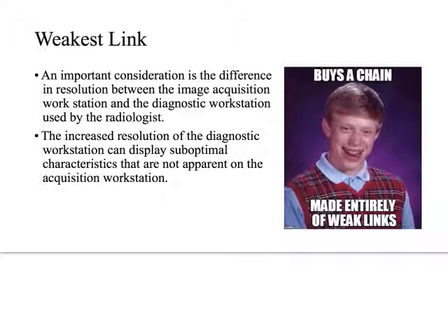So, of course, as I've hinted at, there's always going to be these weakest links in the way that we work with digital technology, and he does a good job of pointing out in this conclusion that whatever the weakest link is, it's going to be what finally limits the image quality that we have displayed in front of us. So this is why the radiologists use a Class 1 monitor at their diagnostic workstations, and also why those monitors are so expensive. And so we need to be careful when we're looking at the images on the Class 2 workstations that we don't think that is the final image.